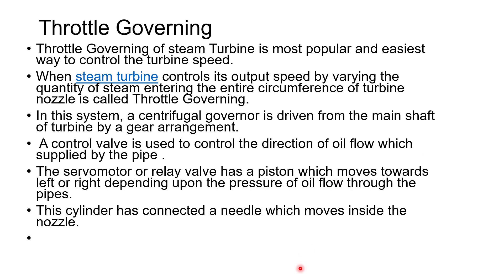Throttle governing of the steam turbine is the most popular and easiest way to control turbine speed. It controls output speed by varying the quantity of steam entering into the entire turbine. In this system, a centrifugal governor is driven by the main shaft of the turbine by a gear arrangement. A control valve controls the direction of oil flow, and the servo motor or relay valve has a piston which moves left or right depending on oil pressure. This cylinder is connected to a needle which moves inside the nozzle.